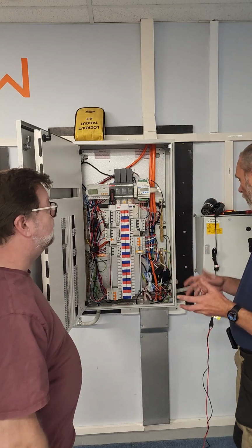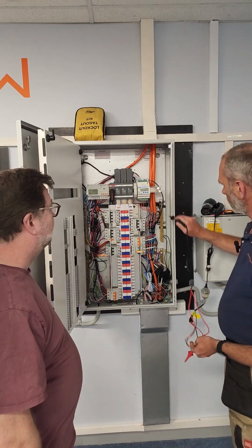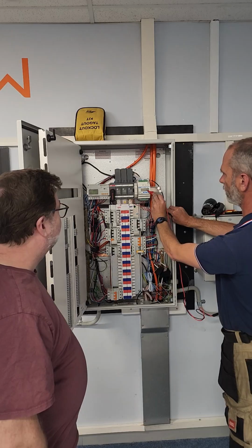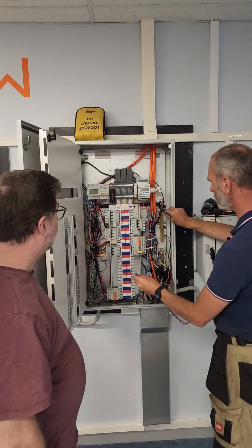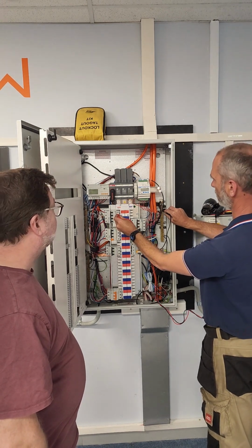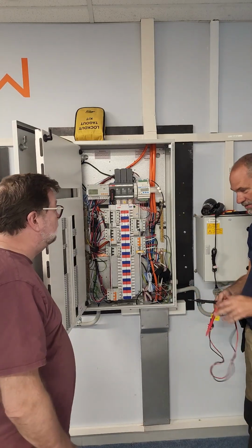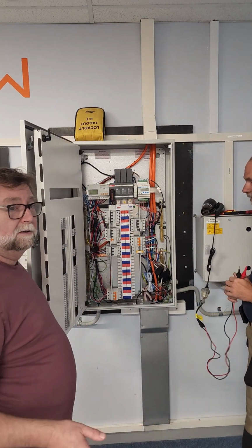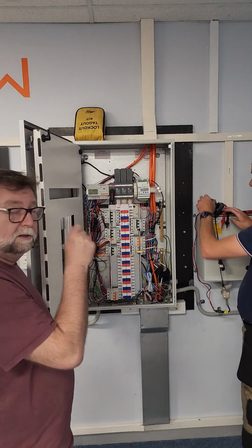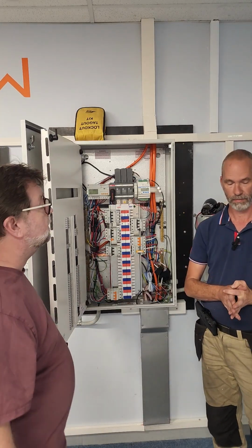So the other one, Graham, I've got the custom special made tool. So you can see here PB, channel 1, 0, because I've got no load on this board. B phase, 1.8 kilowatts. So that's a handy little tool there. Switch your inverter off so you get no power coming back the way. Switch your loads off, and then you use that just to put a load on each phase as required to check phasing. That's a good idea.